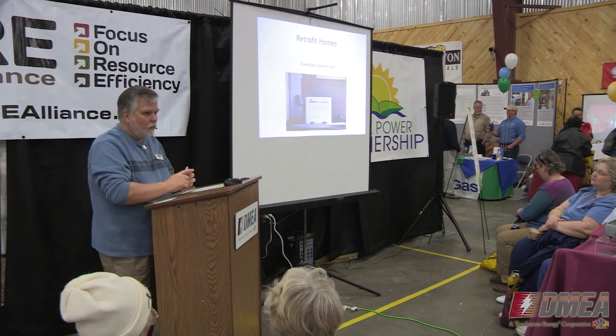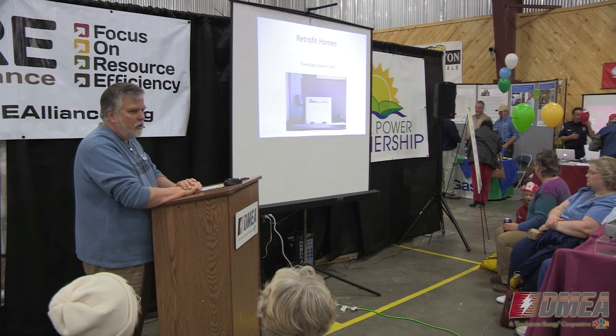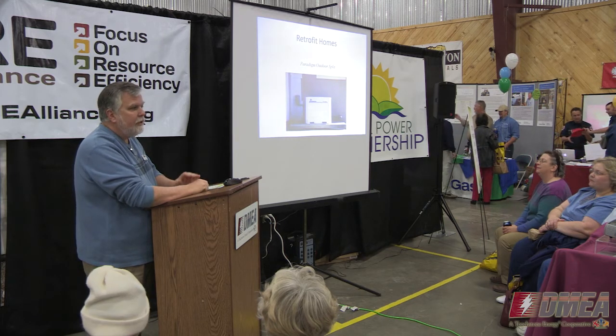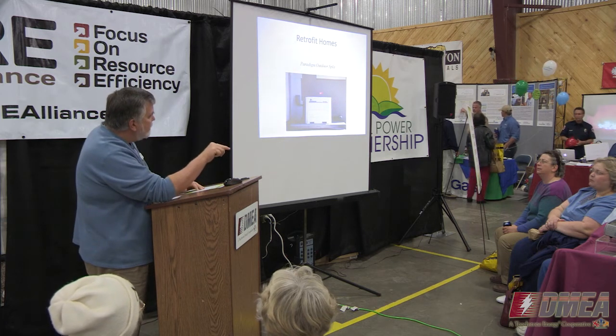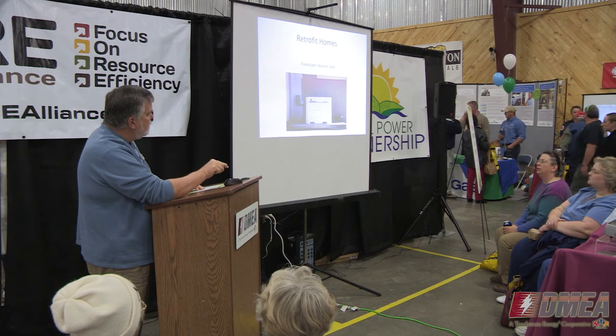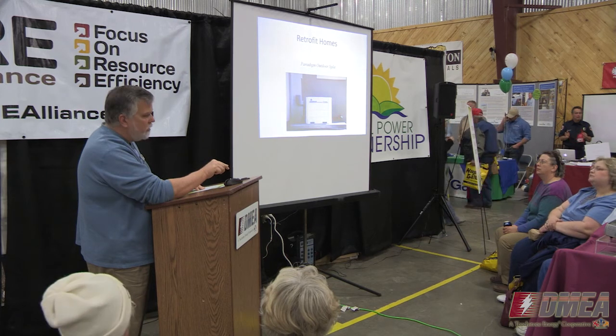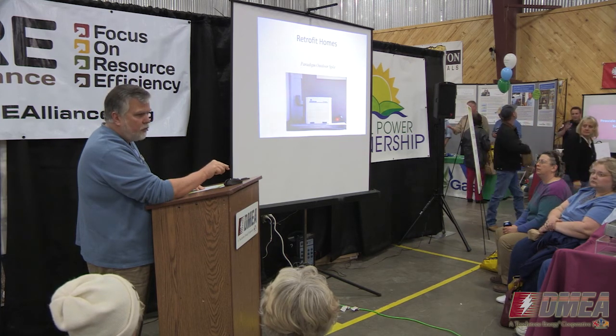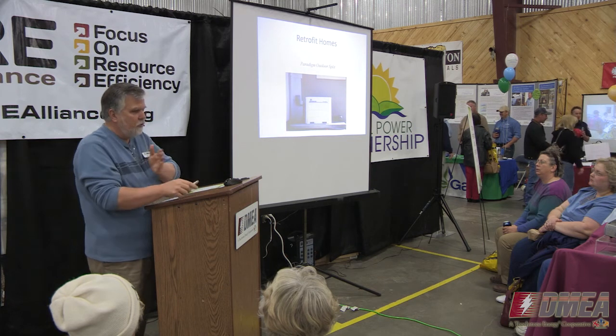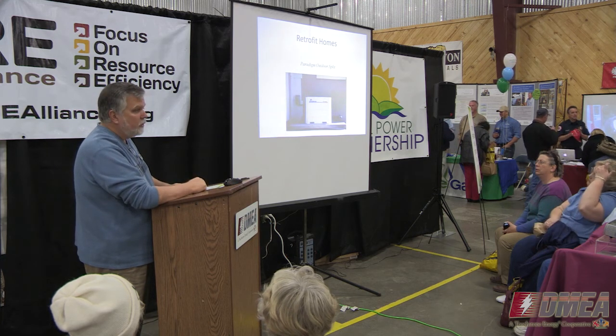If you've got an existing home, one of the ways that we can retrofit your existing home is, if you've got a furnace, if you've got forced air, then we can install a unit that looks very similar to this on a pad outside your house. Kind of looks like an air conditioner. The only difference is we can't see it here, but there's no fan in the top of it. All it really takes on the outside of the house is a pad to put this Geo unit on, and an electrical service to come in and power it. We'll run 2 copper lines into the house that connect to a coil in your ductwork near the furnace. And what you can't see is the 2 Geo pipes coming in out of the ground right here that go out to the loop field. But that's a pretty clean installation there. It's pretty unobtrusive.